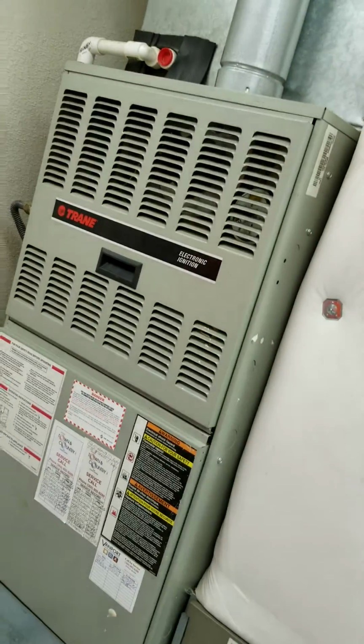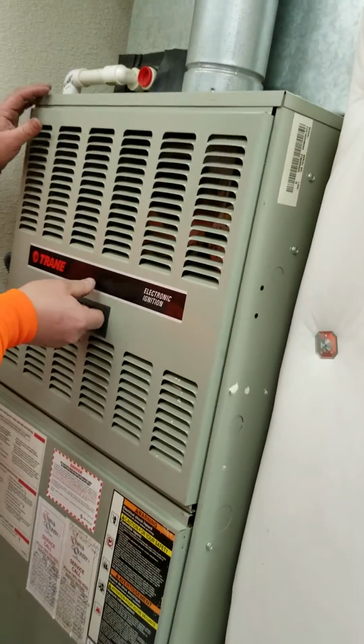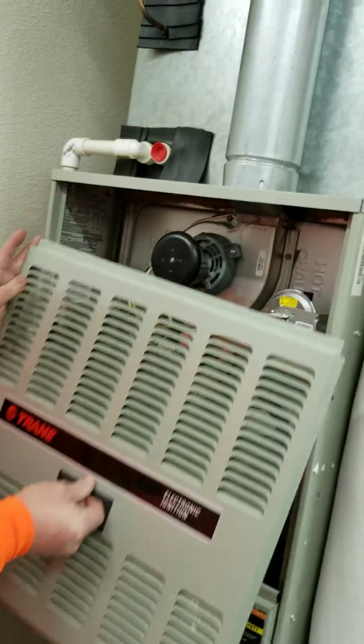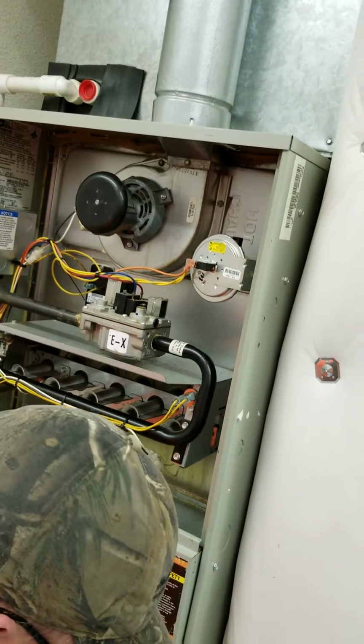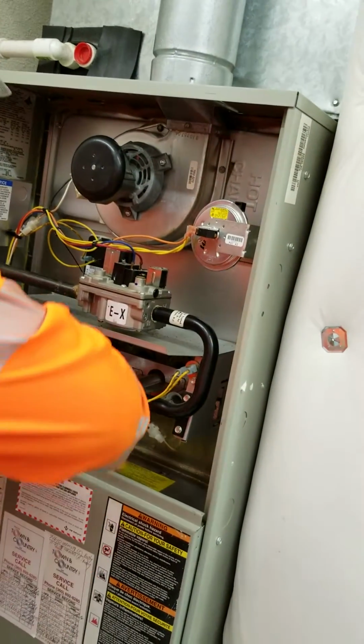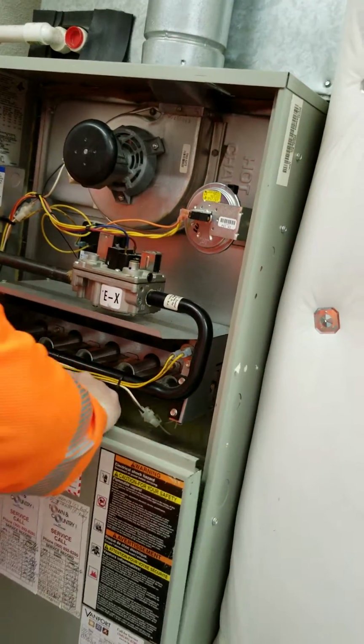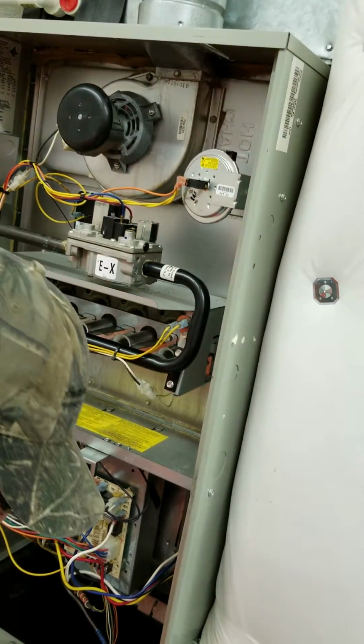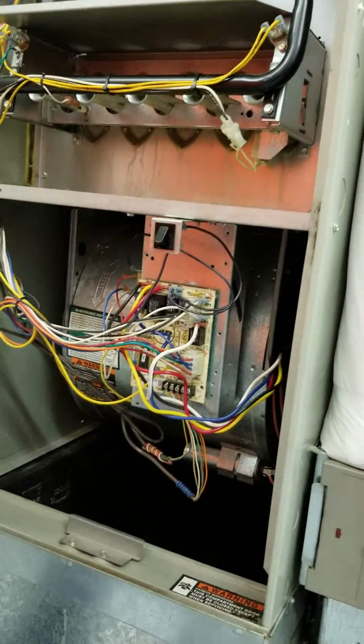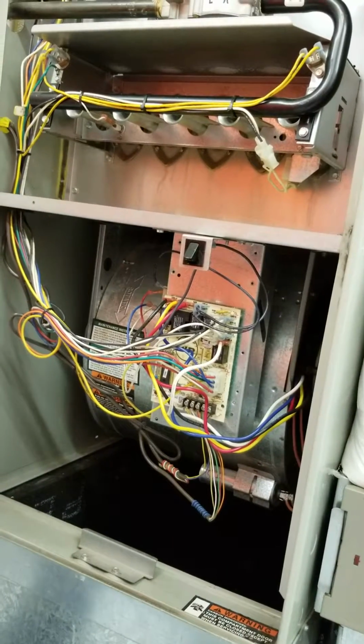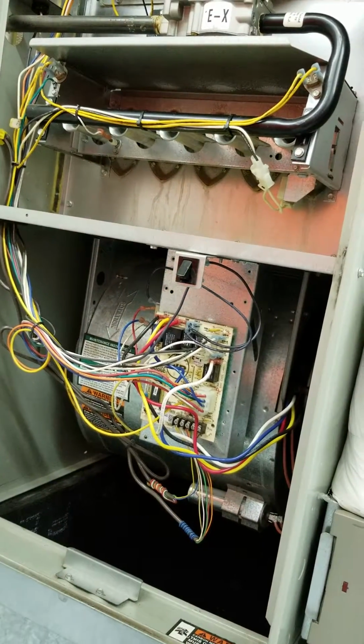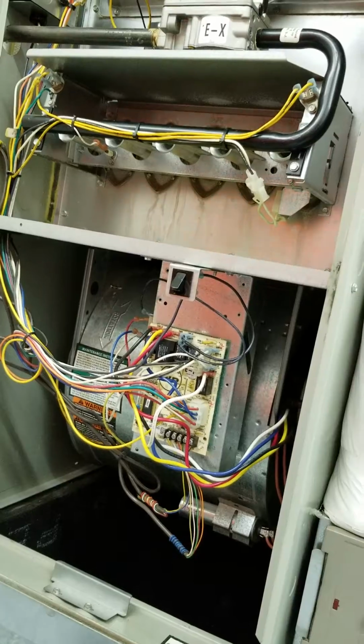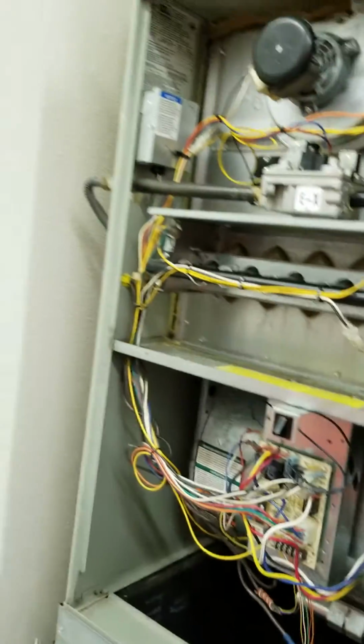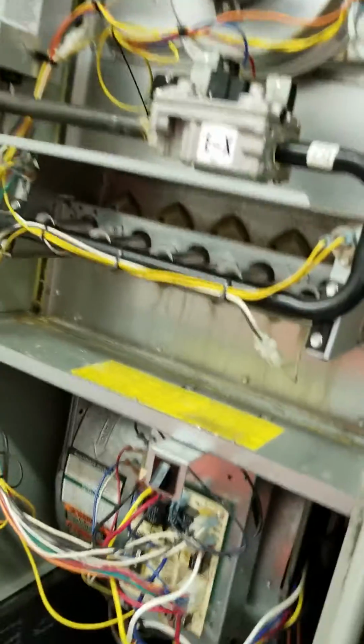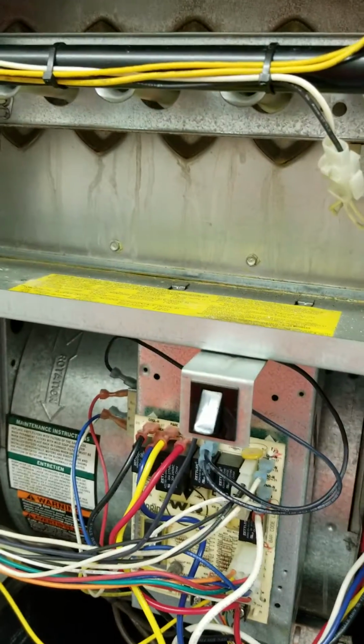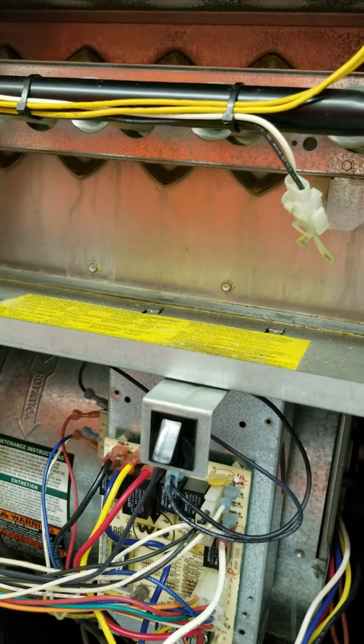Now we're going to go ahead and remove the top panel first. This is going to be access to your burner compartment and pressure switch and draft inducer. The bottom compartment in this upflow furnace is access to the blower assembly and the electronic control board, the ignition control board. So first thing we're going to do, right here, the little black switch in front of you, that is a safety shutoff switch.